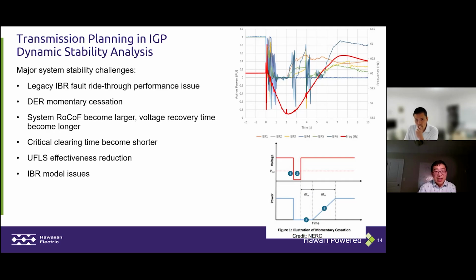In this slide, on the right side upper corner, this plot is from a field event. We had a transmission level 3-phase to ground fault on the Oahu system, which is a 138 kV system. And at that time, all the online IBR went to momentary cessation, or you can see those crazy ups and downs. Basically, system frequency, in this red curve, quickly went below 58.7 hertz and triggered 2 stages of load shedding.